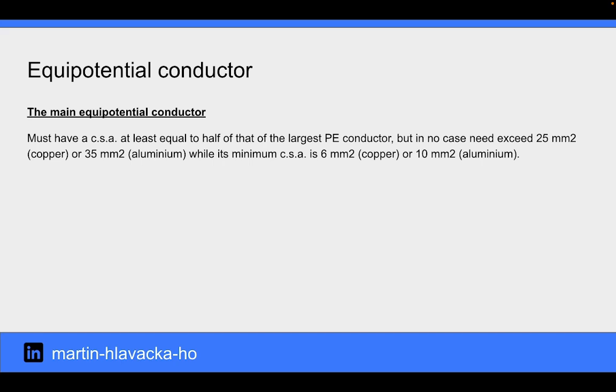The main equipotential conductor must in general have a CSA at least equal to half of that of the largest PE conductor, but in no case need it exceed 25 mm squared for a copper conductor or 35 mm squared for an aluminum conductor, while its minimum CSA is 6 mm squared for copper or 10 mm squared for an aluminum conductor.